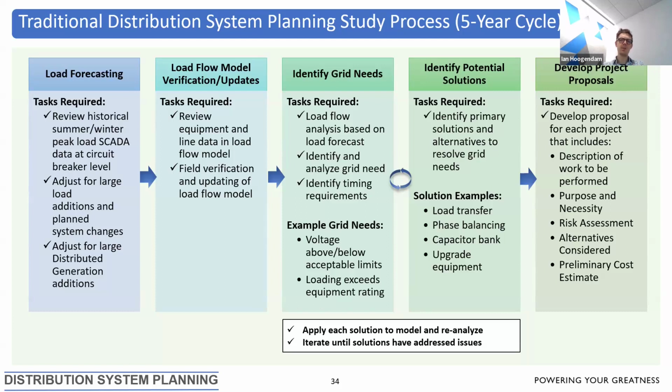And this allows us to estimate what the loading will be on all areas of the model, not just the measured points. We run a power flow simulation that estimates how power is flowing on those distribution circuits. And that allows us to determine if there are any grid needs anticipated due to the load growth that we forecasted.